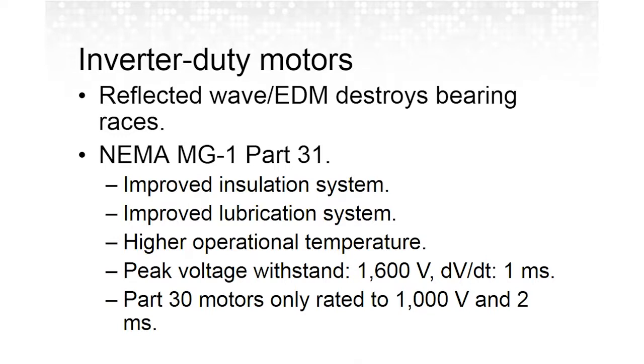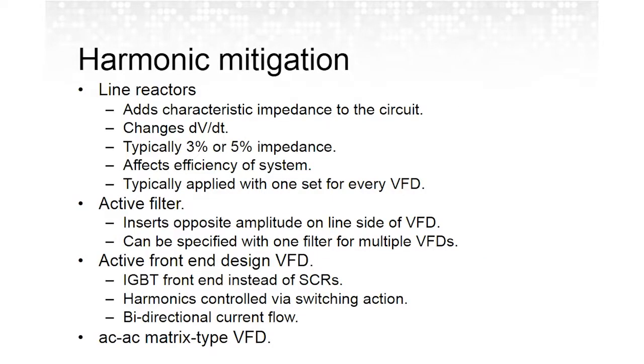Again, the Part 31 standard doesn't really address mitigation of harmonics. It's just basically armor plating the motor. Things like shaft rings address the actual issue of reflective wave. Moving on to the next slide, harmonic mitigation. There are a couple of ways that we can address harmonics coming from a VFD.